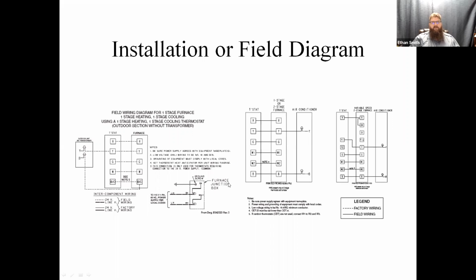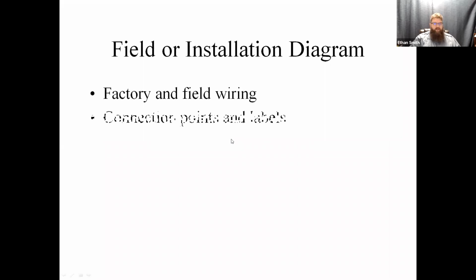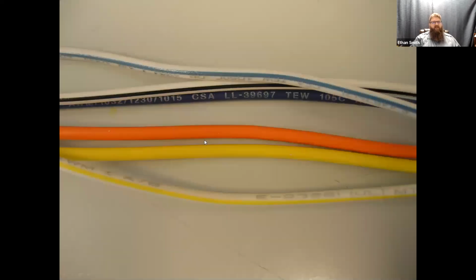So an installation or field wiring diagram just takes that wiring down to the bare bones of what the installer needs to do. Okay. So the installer on this one needs to run thermostat connections and line voltage connections. They'll usually have a couple different options for the low voltage configurations, depending on what you're doing, what you're connecting to. We've got our little legend down here that tells us what each of the different wiring designators are. Okay. Tells us what we're doing. And this is just bare bones. This is what you need to make the thing run wiring diagram. Not terribly useful for diagnostics typically. But it's just going to give you your factory field wiring diagram. It's going to have your wiring points, your connection points, labels, and things like that. Wire requirements are also listed there typically. Sometimes it'll have colors.